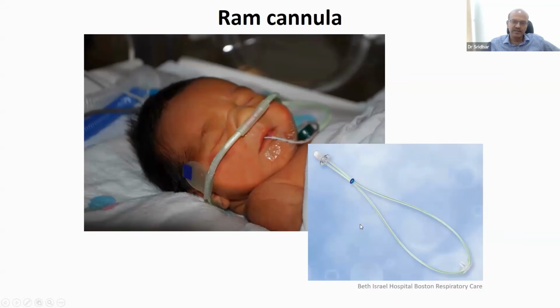So there is an intrinsic resistance in the circuit, and the compliance of the circuit can be variable as well. For this reason, Professor Ramanathan says that you have to increase the settings up to 30% compared to the regular interface to deliver the same pressure. So in general terms, once you use the RAM cannula, it works, but the pressure you need may have to be increased because there is a resistance in the circuit. For example, if we start NIPPV at 20/5 with the regular machine, when you're using the RAM cannula interface, you may go to 22 or 23 and a PEEP of 6 or 7, the CPAP pressure. In a bigger baby, you can go to 30s of PIP and 7 to 8 of PEEP as well.